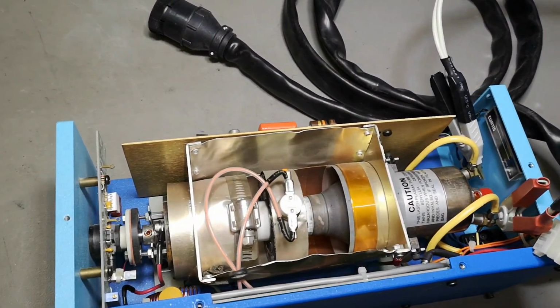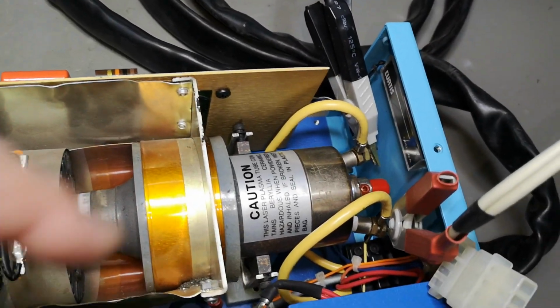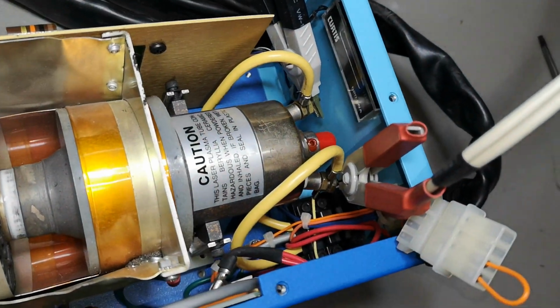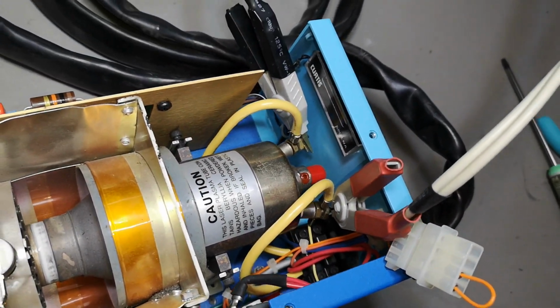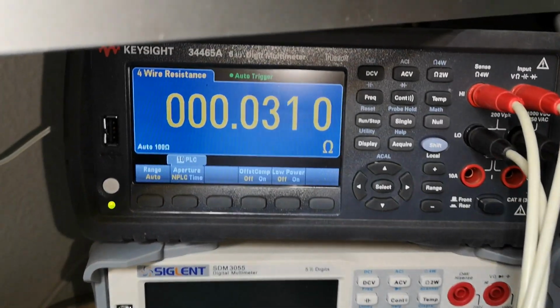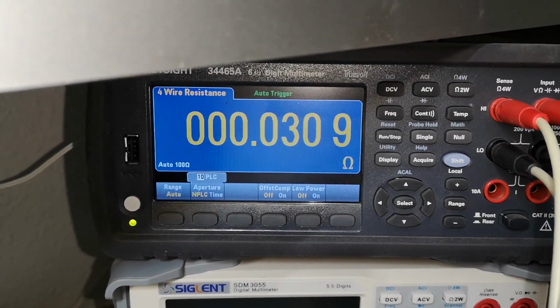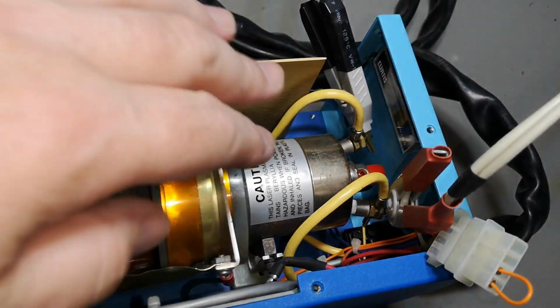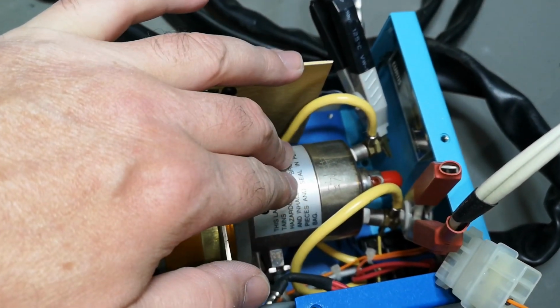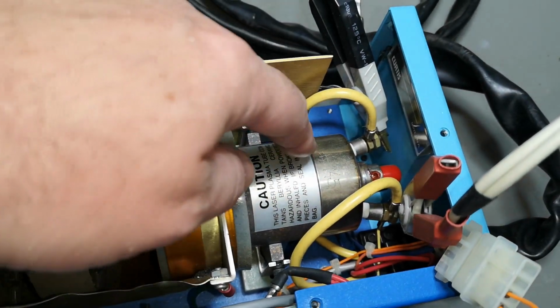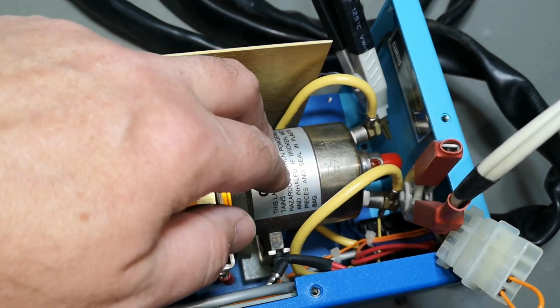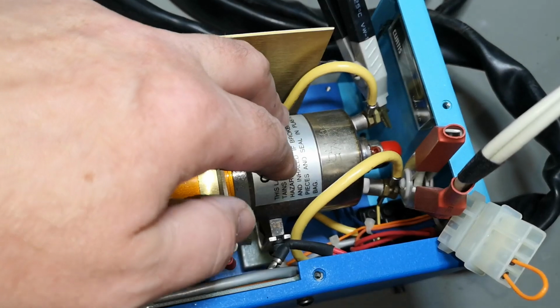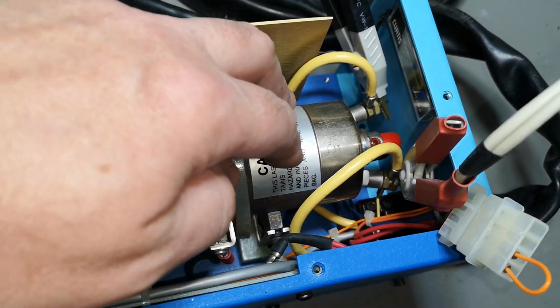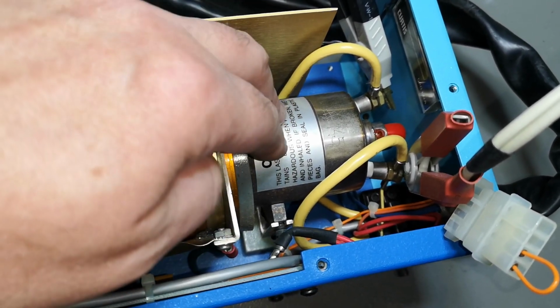So first I want to play a little bit with the filament. Now I'm measuring with a 4-point ohm meter, and we got 30 milliohms. I actually believe this is normal, because you can imagine this is a cold filament, and the filament wire is made just like a bulb - the warmer it gets, the higher resistance you get.